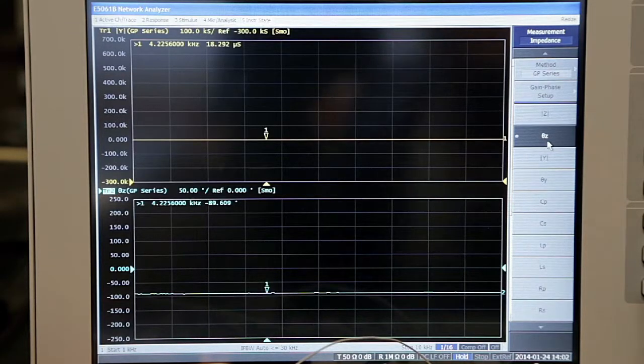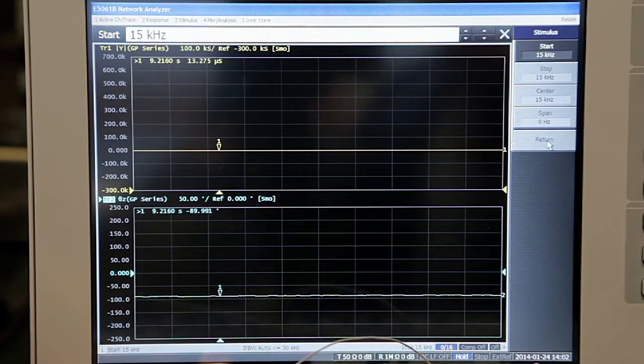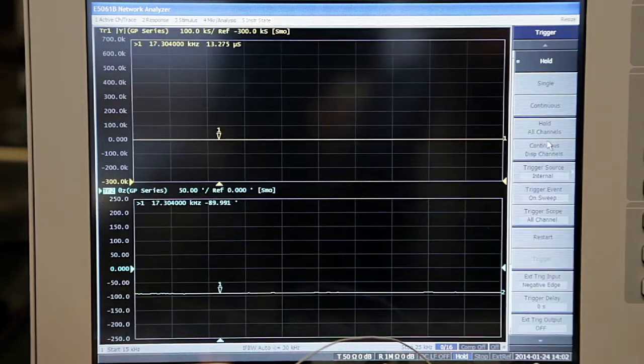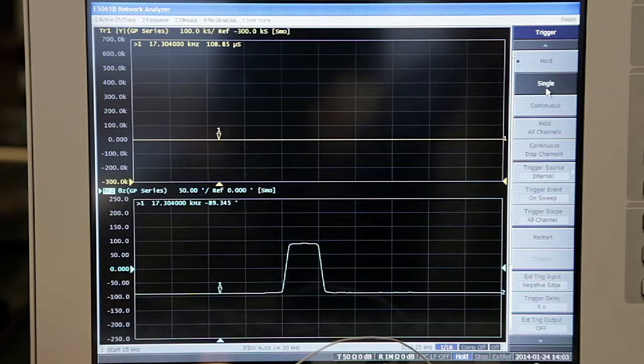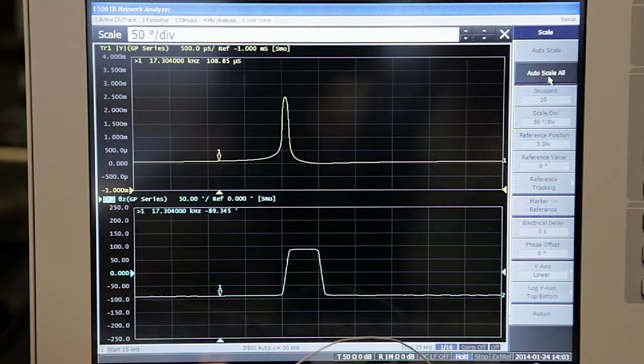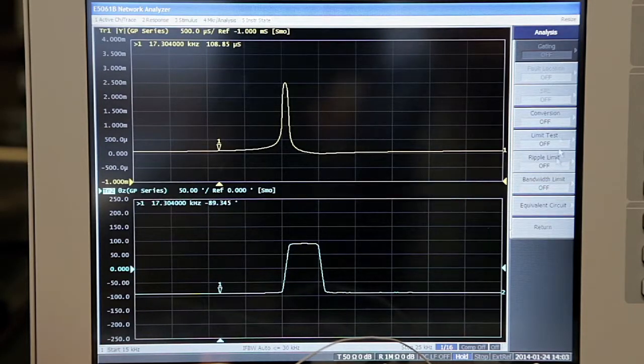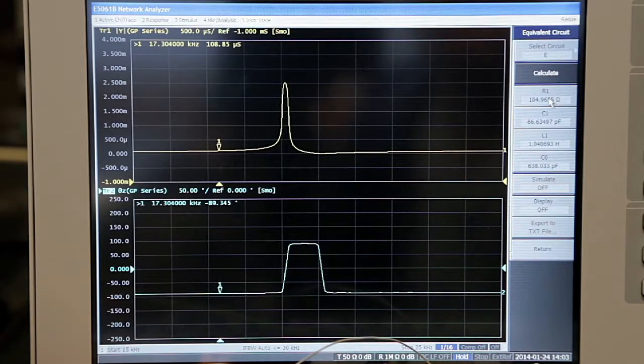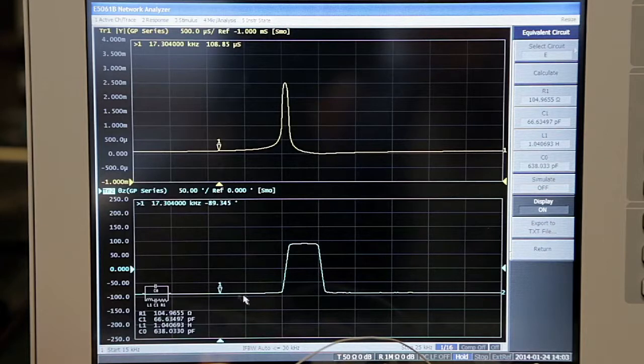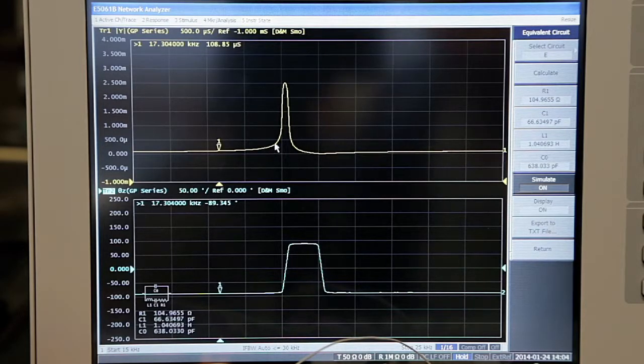I'm going to change the start to 15 kHz and the stop to 25 kHz, then go ahead and do a single sweep, and now let's do our auto scale. So there's Y and theta. In order to do the equivalent circuit, under analysis I'm going to pick equivalent circuit. I need to make sure I pick the correct circuit — in this case it's E — and I'll hit calculate. Here are the values for R1, C1, L1, and C0. If I turn the display on, it'll show the actual circuit with the components and their values. And if I turn simulate on, it overlays a plot of the simulated circuit.